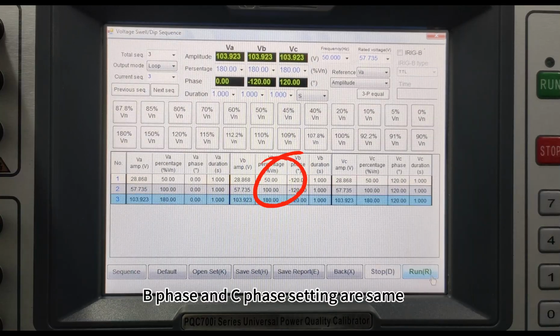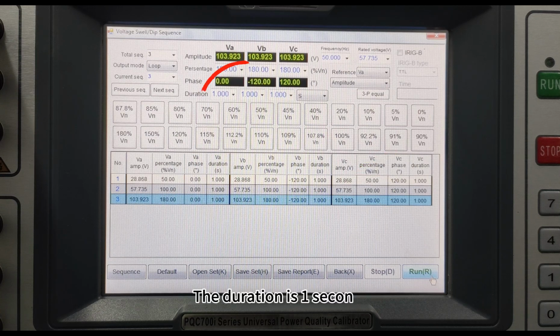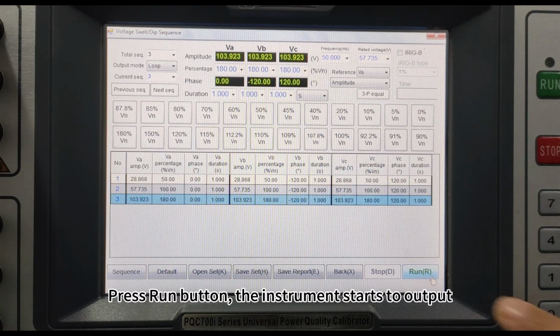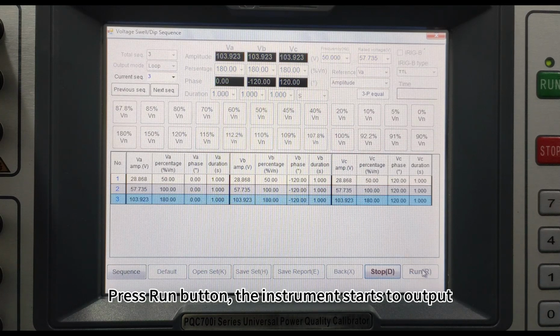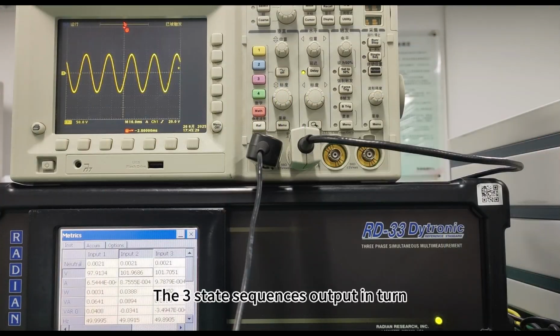B phase and C phase setting are same. The duration is 1 second. Press Run button, the instrument starts to output. The 3 state sequences output in turn.